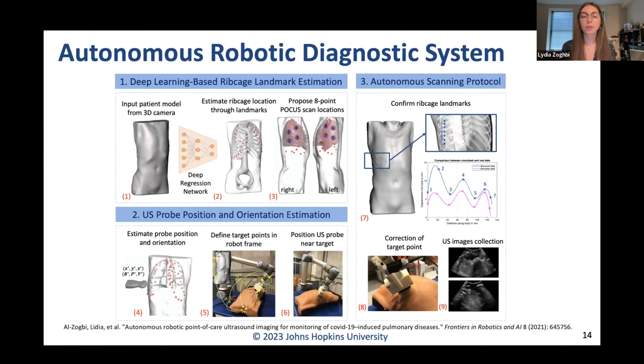So this is based on the hypothesis that a displacement of the ultrasound probe into the patient body on the rib is going to be smaller for the same amount of force as opposed to the displacement into the body in between the ribs, which makes sense because as the ultrasound probe is in between the ribs, there's more soft tissue. So you're going to be able to go a little bit deeper into the patient for the same amount of force. And really, we showed that it works well in practice, and we've collected some data on that. And then once we identify the larger displacement, we drive the ultrasound probe to that location, collect the ultrasound images, and relay them to the clinician.